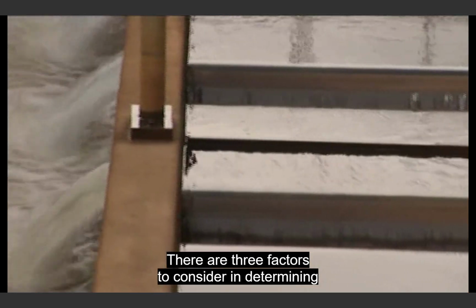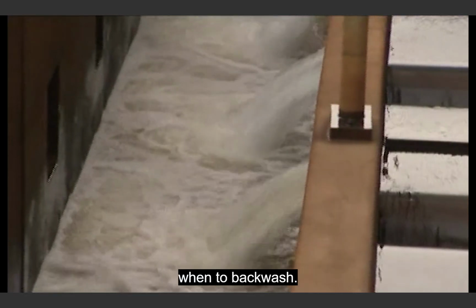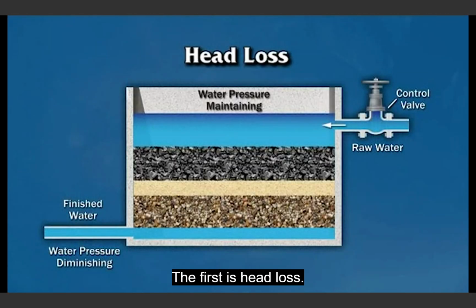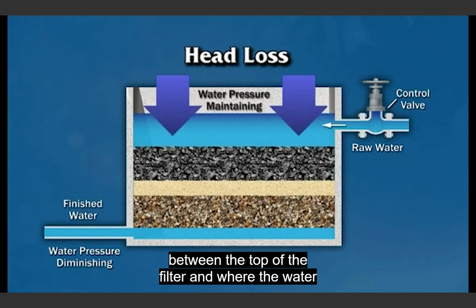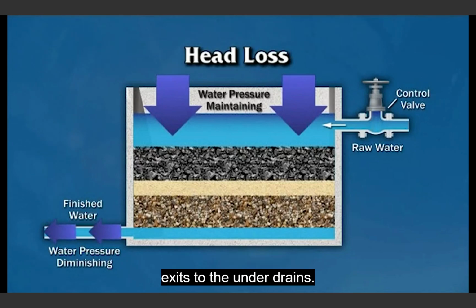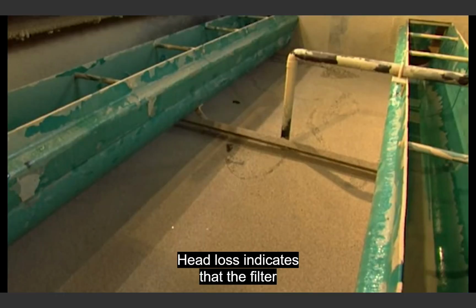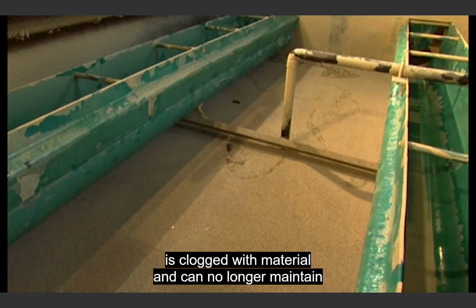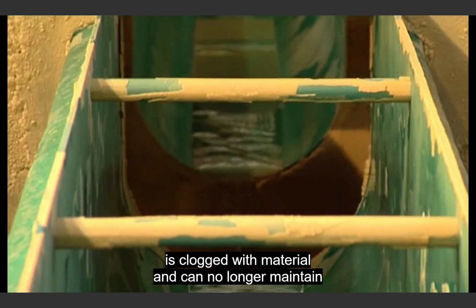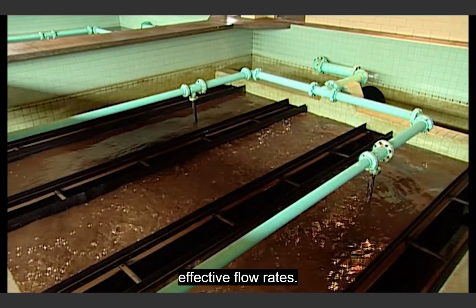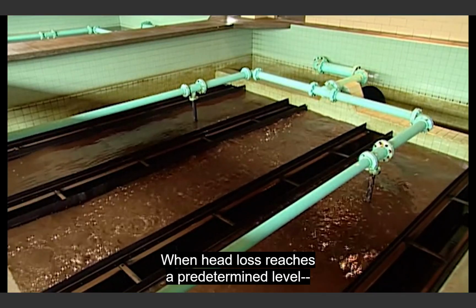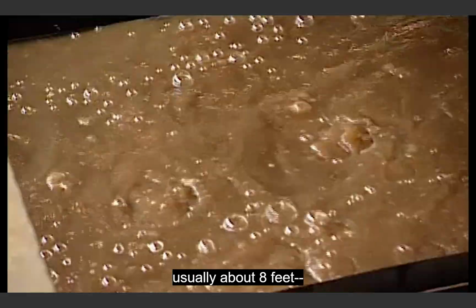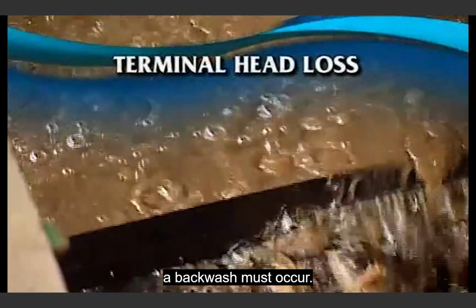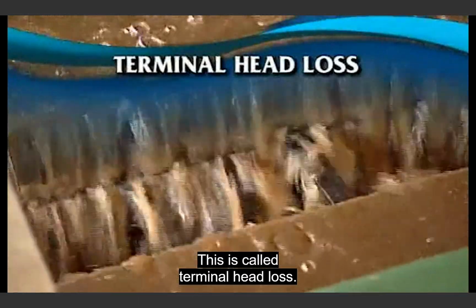There are three factors to consider in determining when to backwash. The first is head loss. This is the difference in pressure between the top of the filter and where the water exits to the underdrains. Head loss indicates that the filter is clogged with material and can no longer maintain effective flow rates. When head loss reaches a predetermined level, usually about 8 feet, a backwash must occur. This is called terminal head loss.